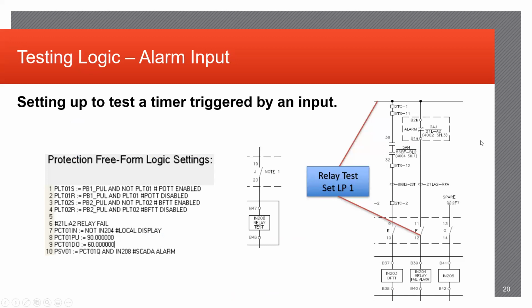So setting up an alarm input. In this case here, we're actually going to be utilizing the output contacts from your test set going back into the relay. You can see the test set is going to be connected from any high side current voltage source for the DC side, going directly to the top side of the input that you're going to be testing. And as long as you have a return path on the other side of your input, then you can complete the circuit and verify that the correct input picks up.